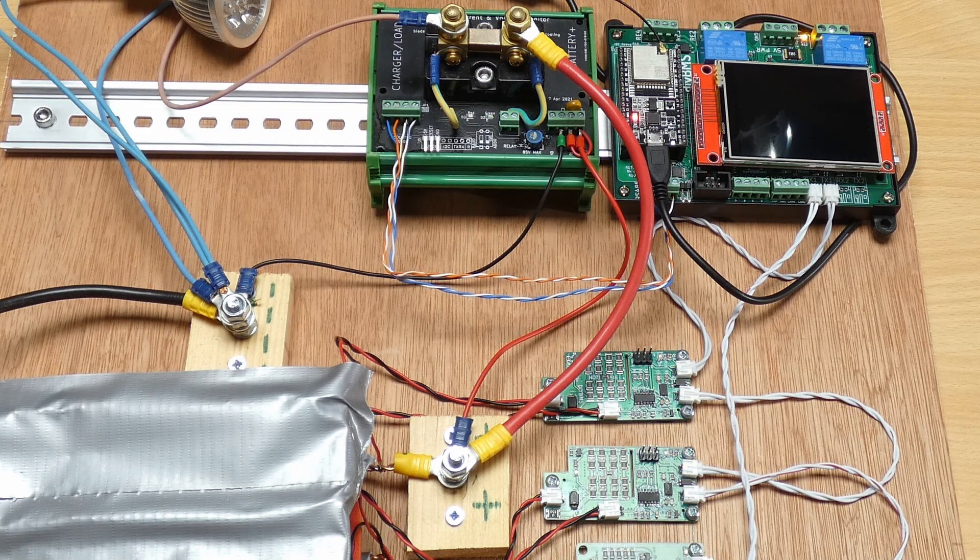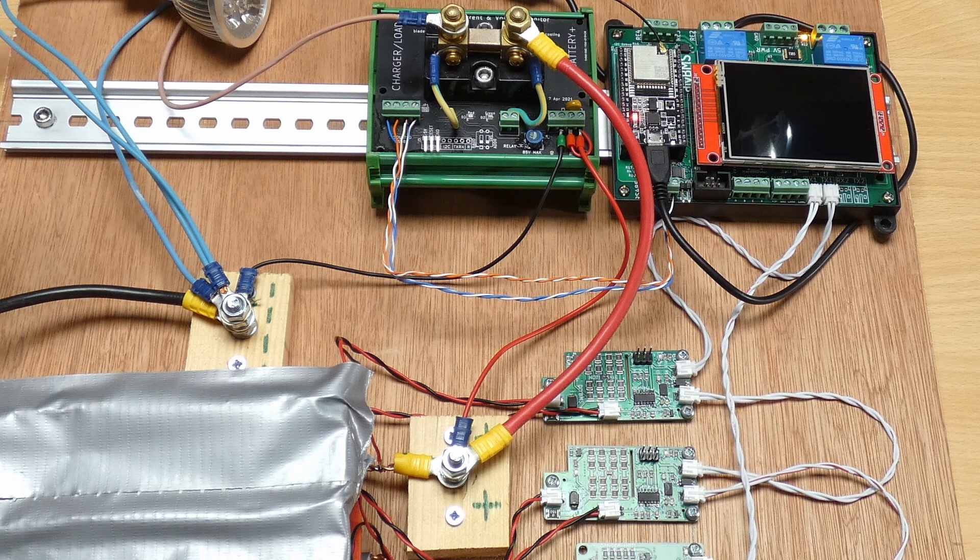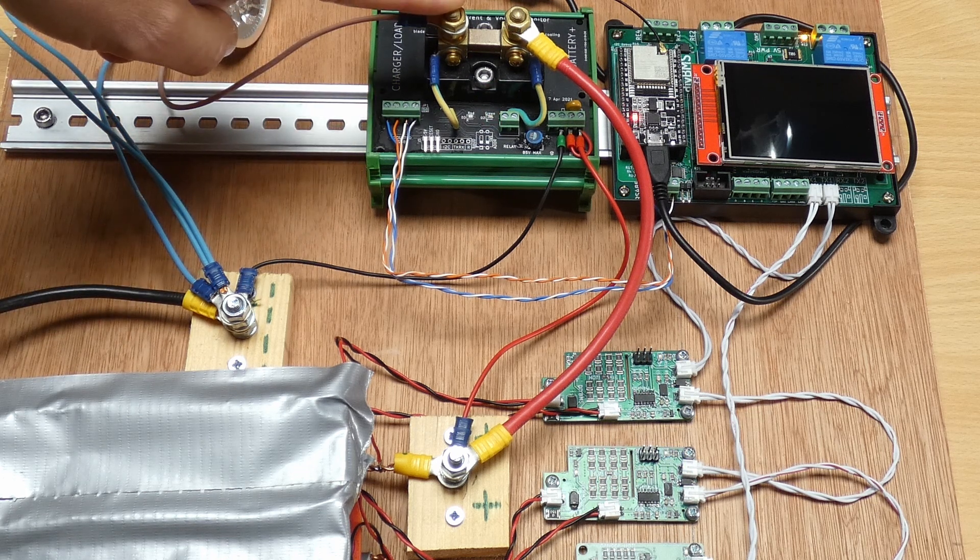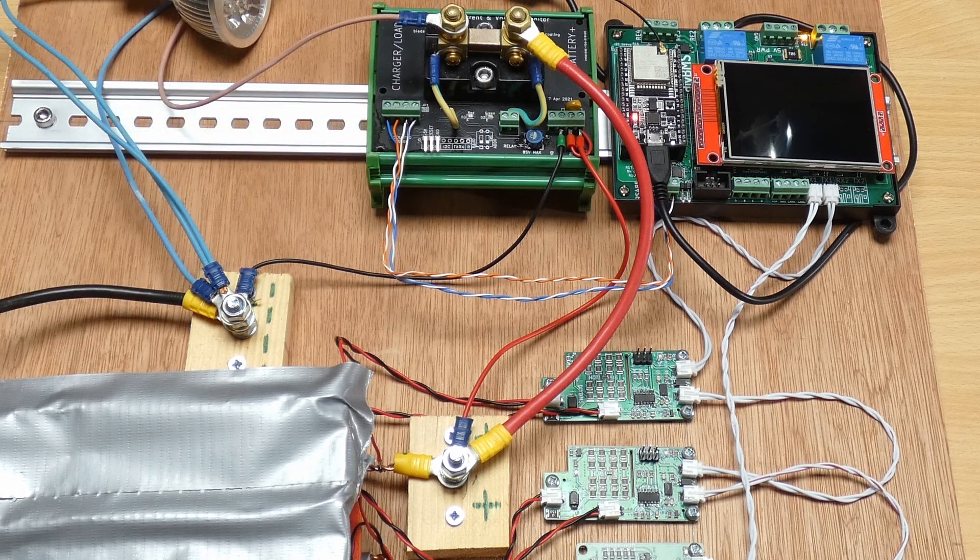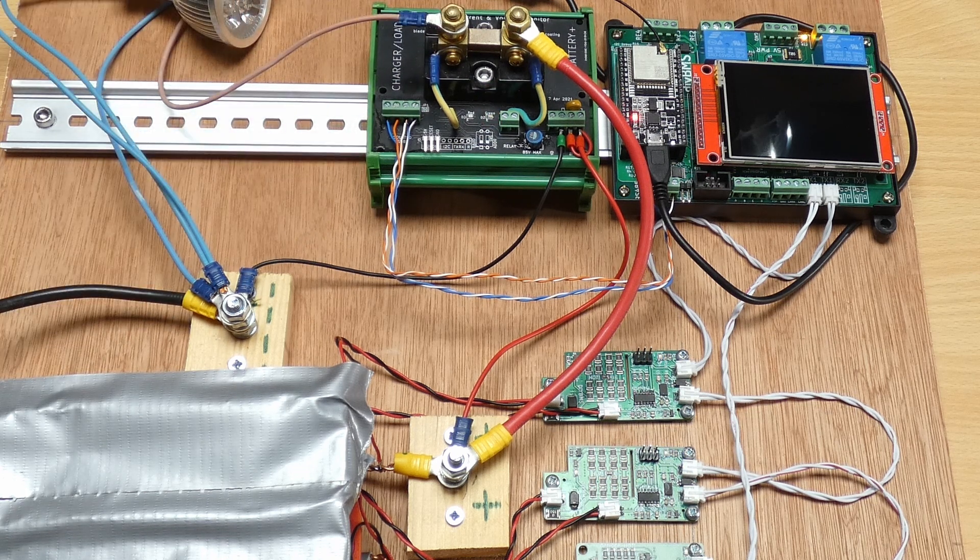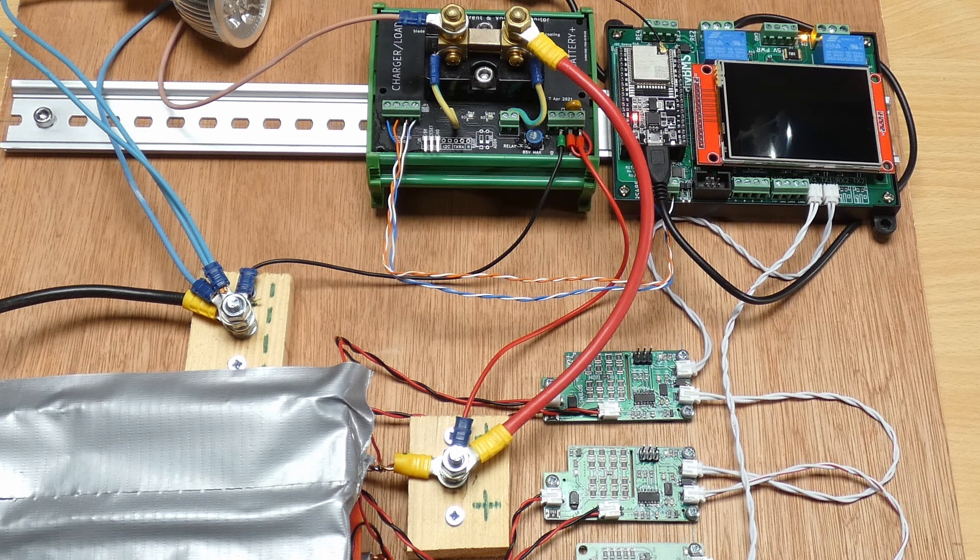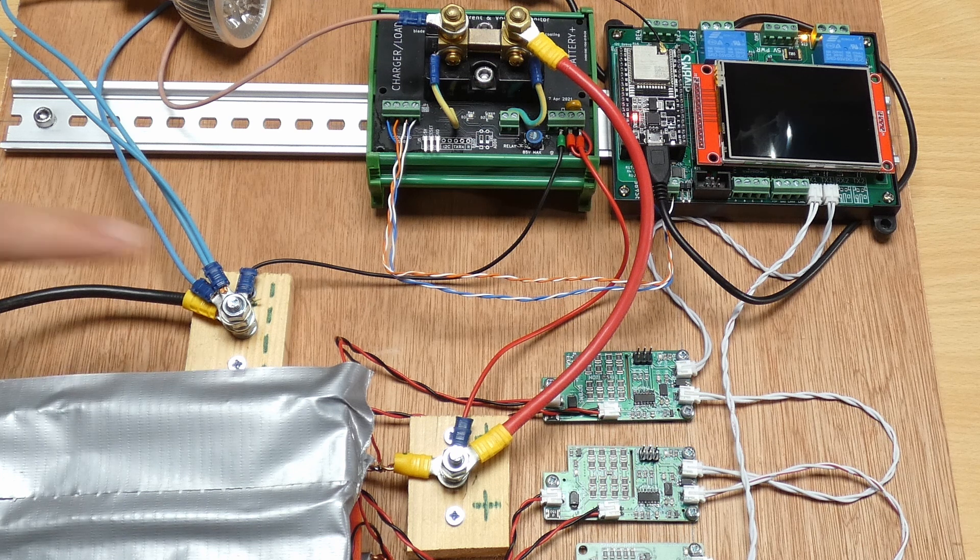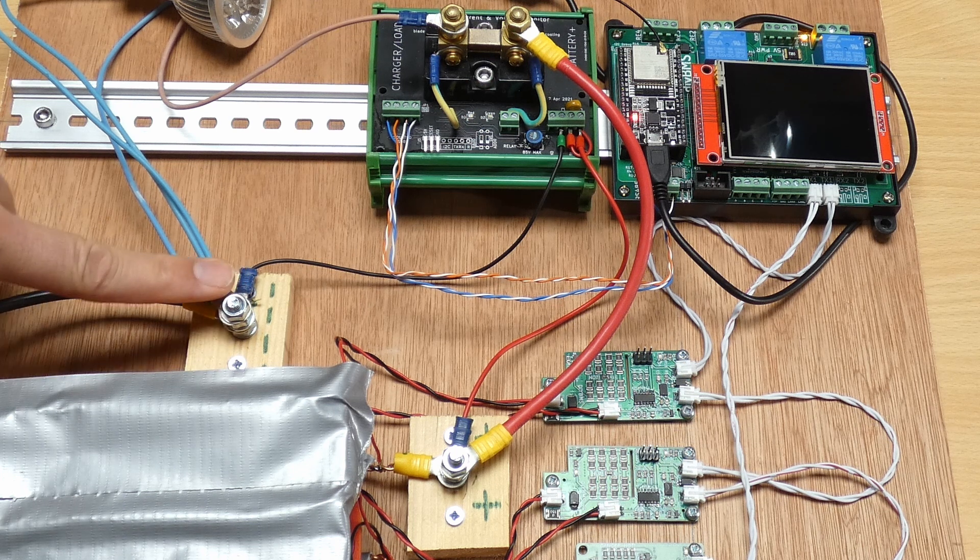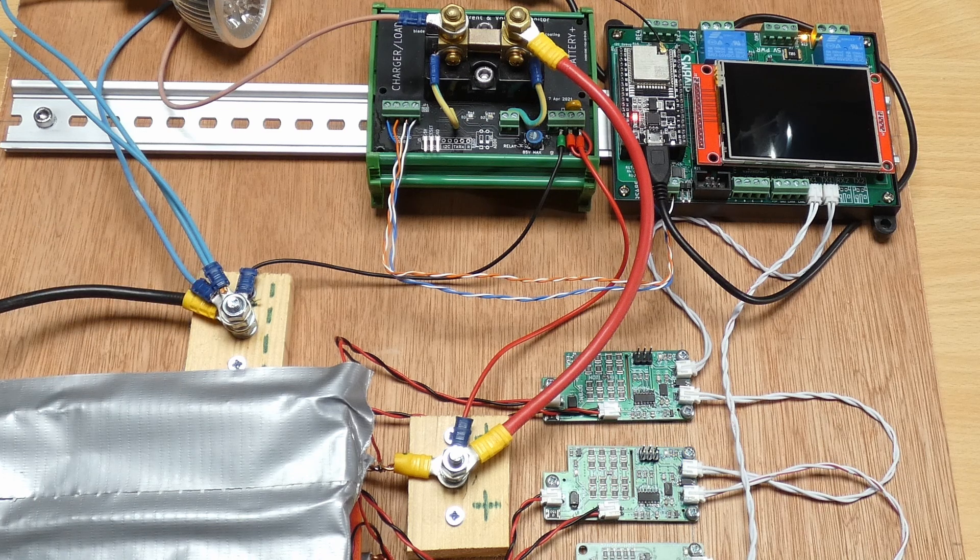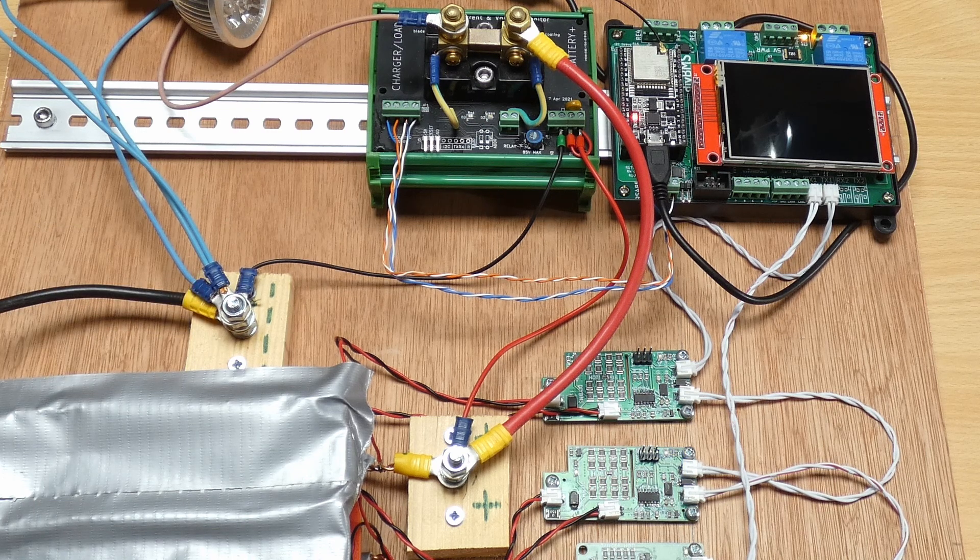On the left side of the shunt all the generators and consumers of energy are connected. Anything connected on this side of the shunt will be measured by the current monitor when it generates or consumes the energy in the battery. And finally all the negatives are joined together on this one stud.